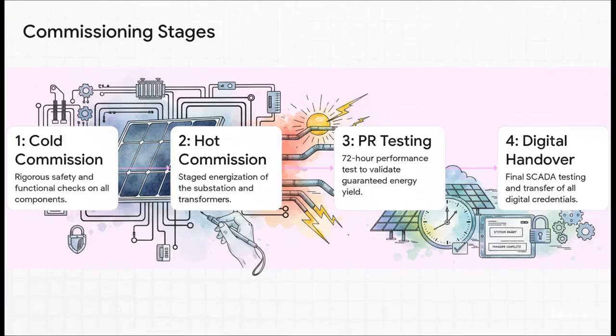The commissioning phase is incredibly meticulous. First, you have cold commissioning, where every single connection and component is tested without power to make sure it's all safe. Then comes hot commissioning, where the system gets energized in careful stages. But the real test, the big one, is the 72-hour performance ratio test, which proves the plant can actually deliver the energy it's contractually promised to. Only after passing that test is it officially handed over.